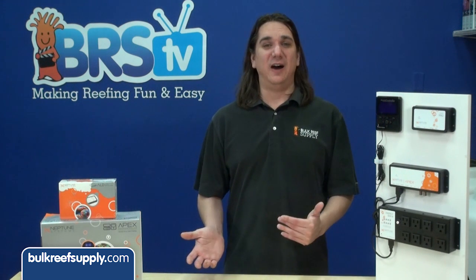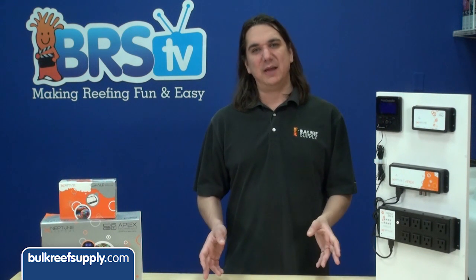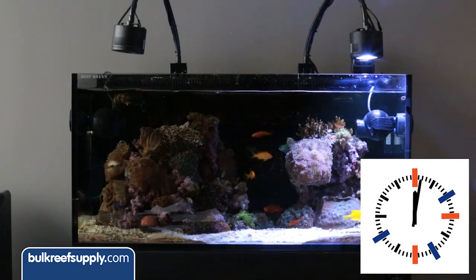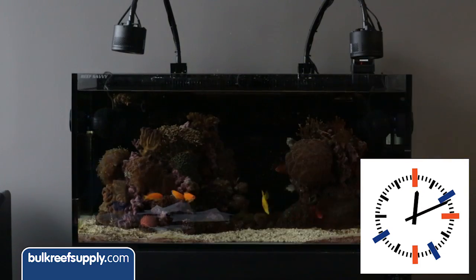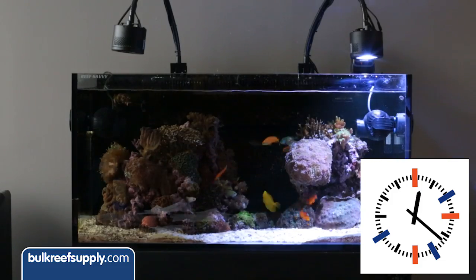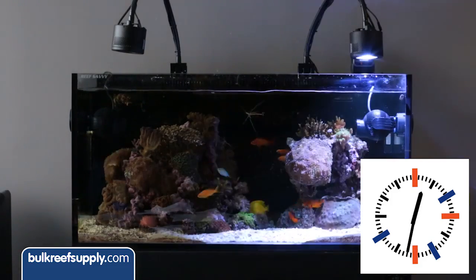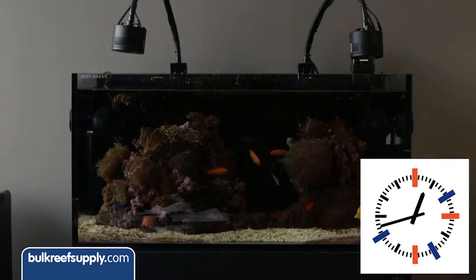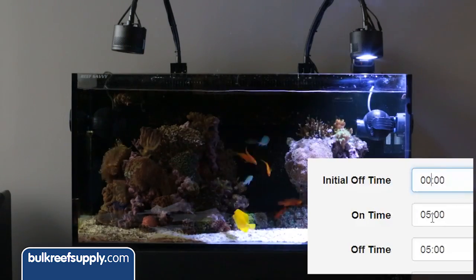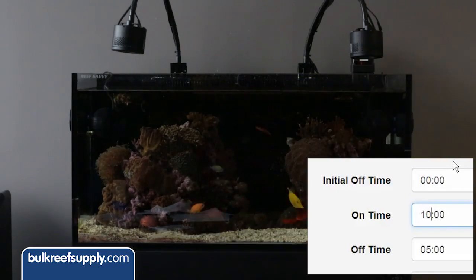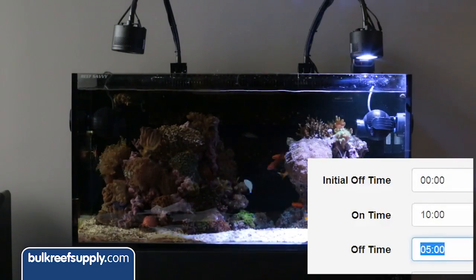The off time is how long you want the pump to be off during the cycle. So if I wanted the pump to start immediately when the cycle starts at midnight, turn on for 10 minutes, off for 5 minutes, and continue this cycle for the entire day, I would enter zero for the initial off time, 10 for the on time, and 5 for the off time.